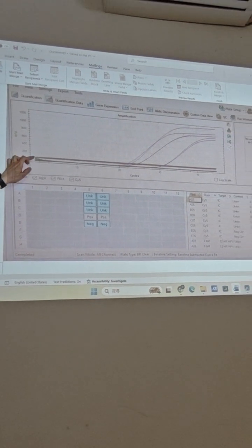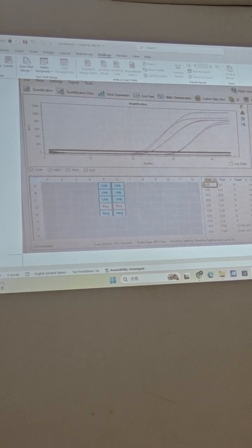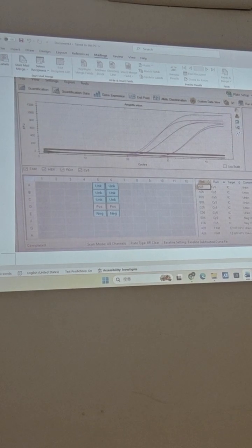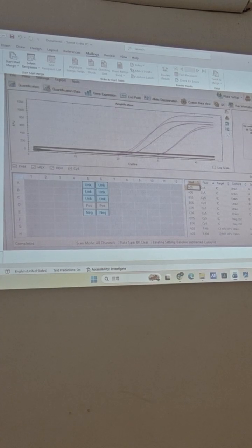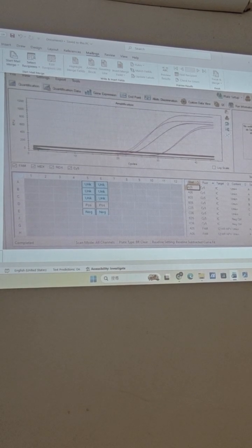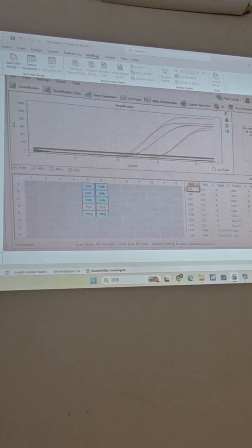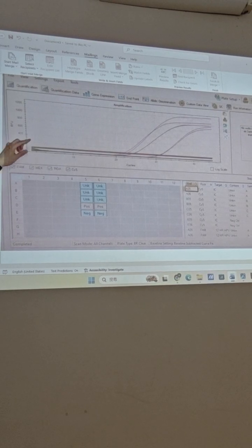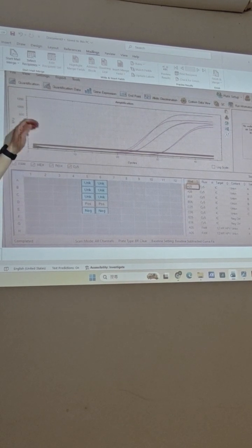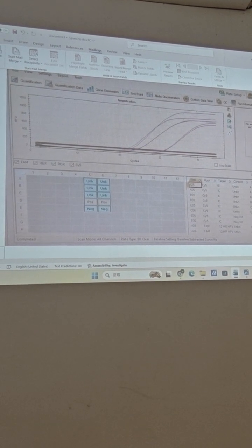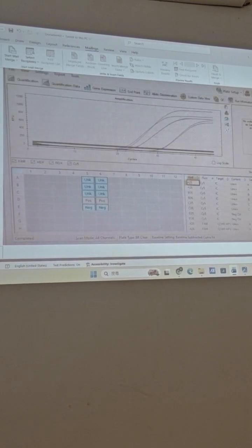You cannot apply this number to another test because sometimes the sample background is not okay. Maybe there is a lot of mucus, a lot of other material in the sample, which can also affect the noise. And also remember I told you about the machine: every time it is not the same. The light source, everything will change. So that's why you cannot use this number. Maybe sometimes you need to adjust a little bit higher or a little bit lower, depending on the lab. So this is not a standard curve, so you need to adjust every time.